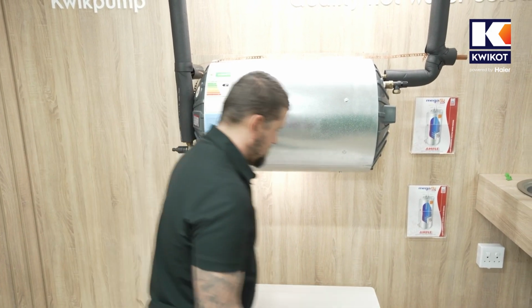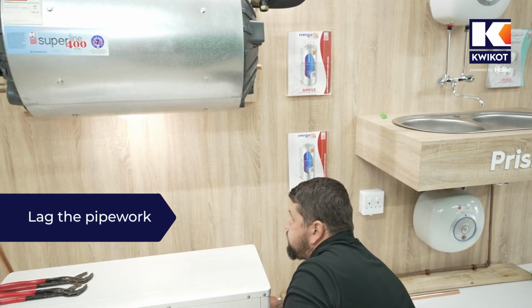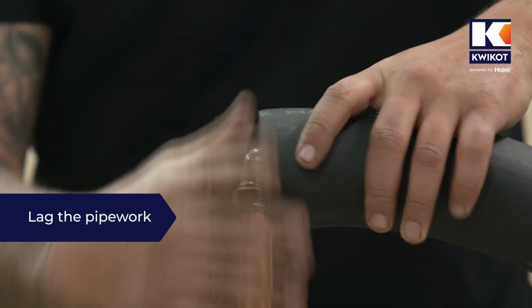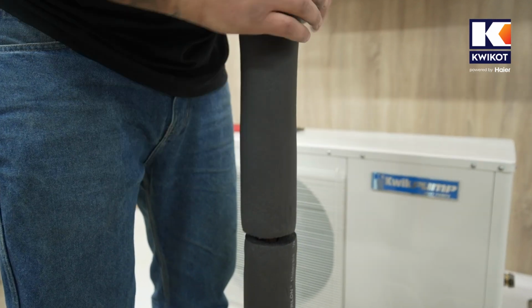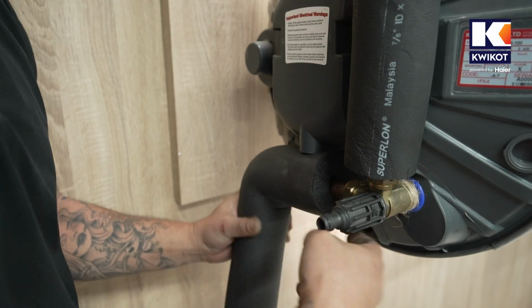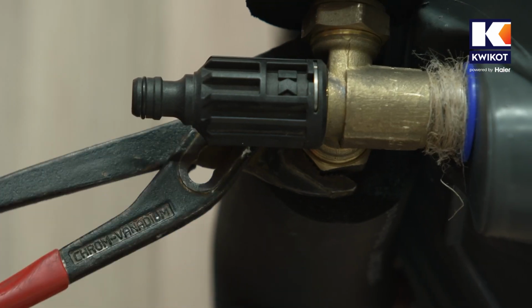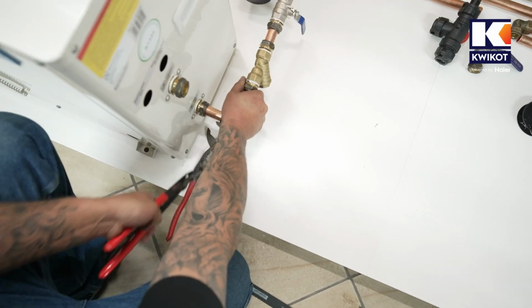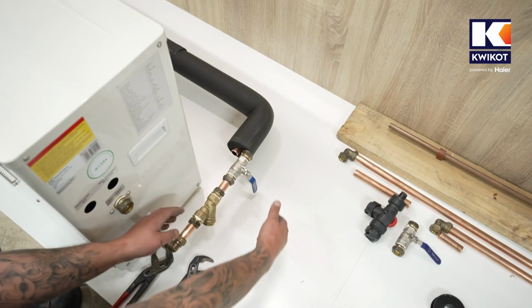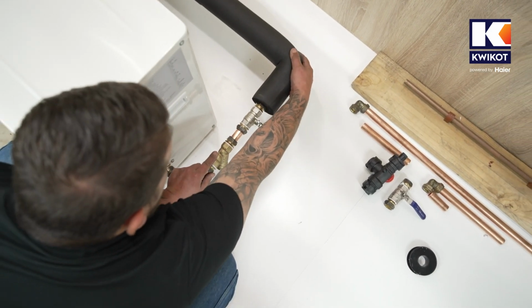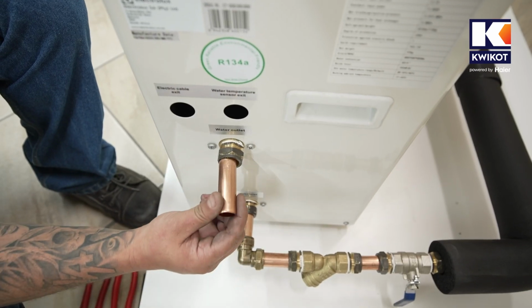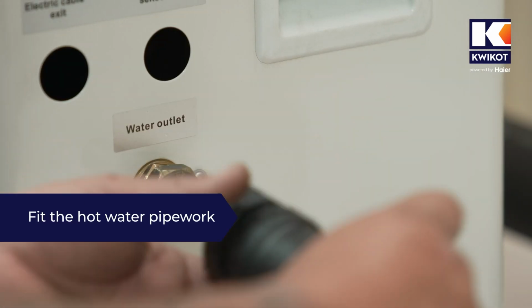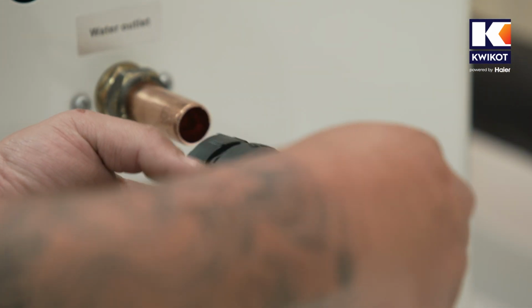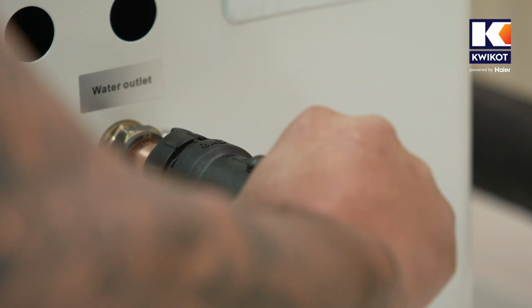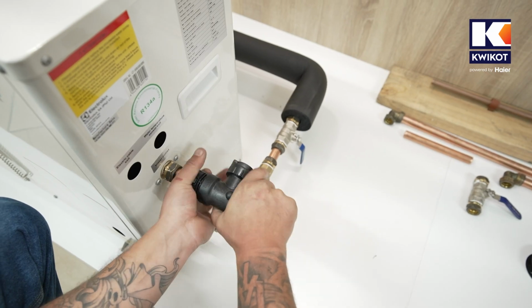Our next step is to remove these 3 lengths of pipe in order to fit R1 lagging around them. And now that the pipework is lagged, we can now refit the top end of the pipe back onto the double drain cock on the water heater, and then loosen the Connex at the heat pump inlet so that we can refit the bottom end of the lagged piping. And then we retighten the inlet Connex. So now we've completed this connection. The next step is to fit the load control valve to the outlet. In this case, we don't need to adjust the setting because it's already set to 55 degrees Celsius. And we can just hand tighten it so that the valve is secure and doesn't move.